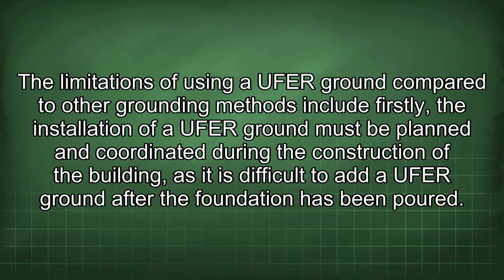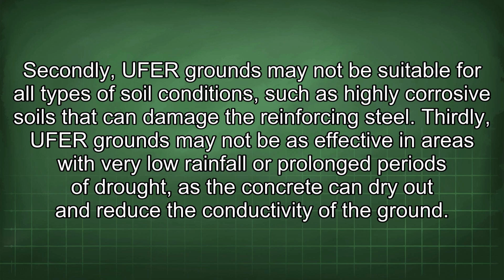The limitations of using a UFER ground compared to other grounding methods include: firstly, the installation of a UFER ground must be planned and coordinated during the construction of the building, as it is difficult to add a UFER ground after the foundation has been poured. Secondly, UFER grounds may not be suitable for all types of soil conditions, such as highly corrosive soils that can damage the reinforcing steel. Thirdly, UFER grounds may not be as effective in areas with very low rainfall or prolonged periods of drought, as the concrete can dry out and reduce the conductivity of the ground.